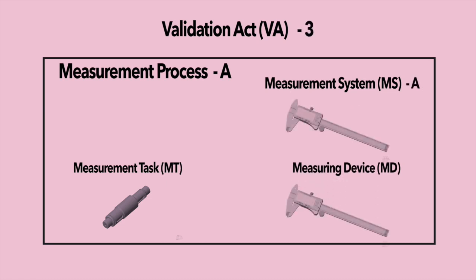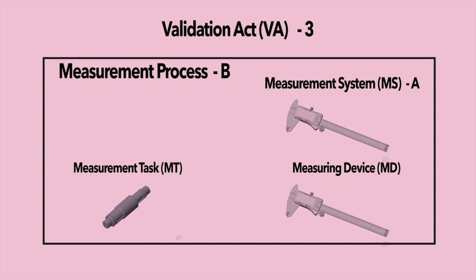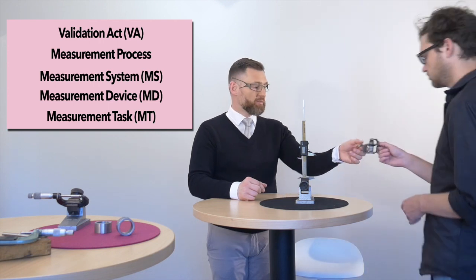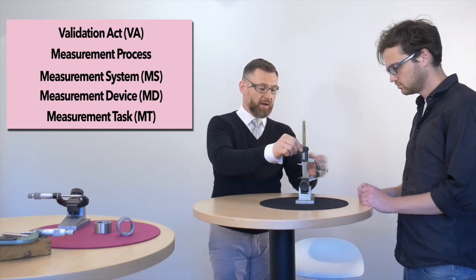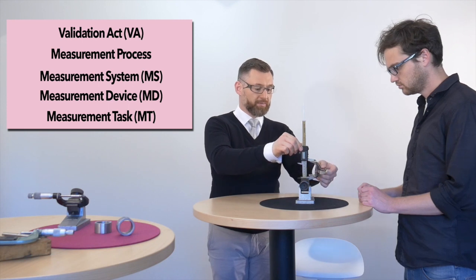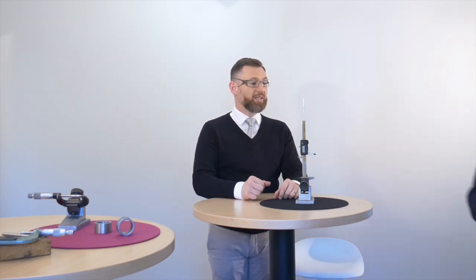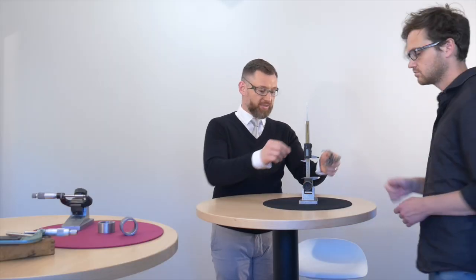Also, it is possible that one measurement system is being used with the same measurement task but in different measurement processes. This is, for example, when one measuring device is being used, but sometimes we measure the part immediately after the machining process, but sometimes we let the part to be cleaned and temperature stabilized to reduce variation for special checks. This is two different measurement processes that also require separate validation acts.